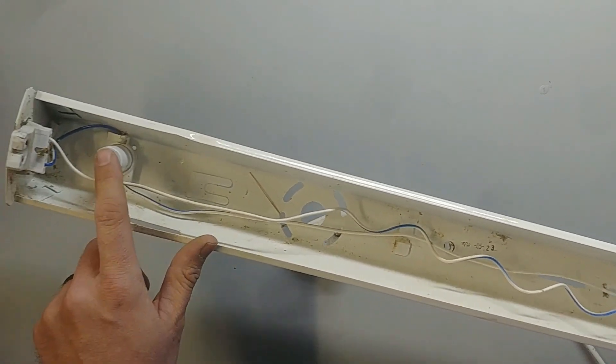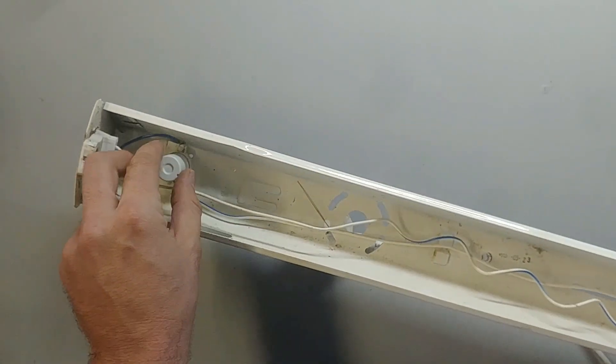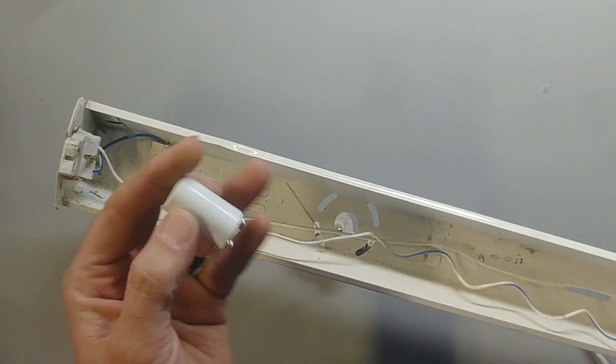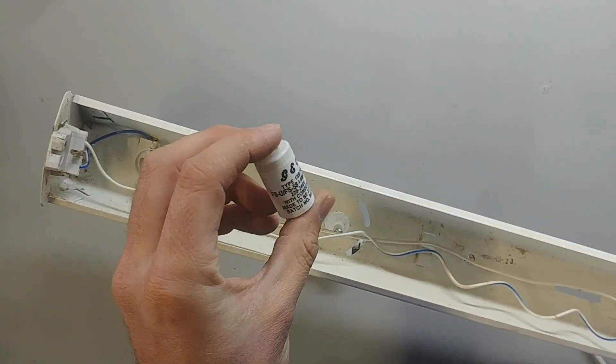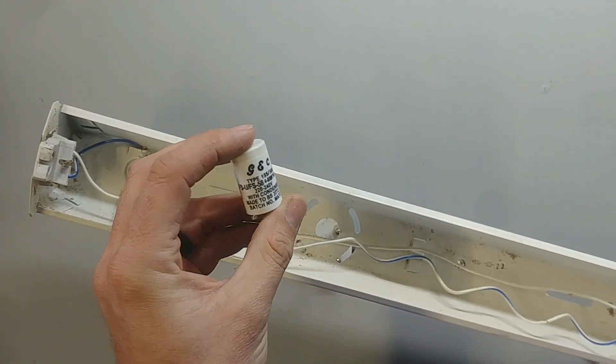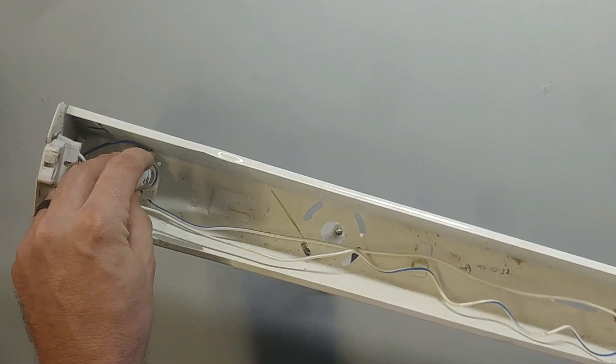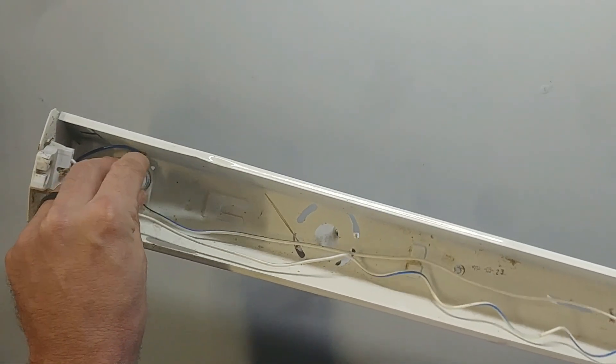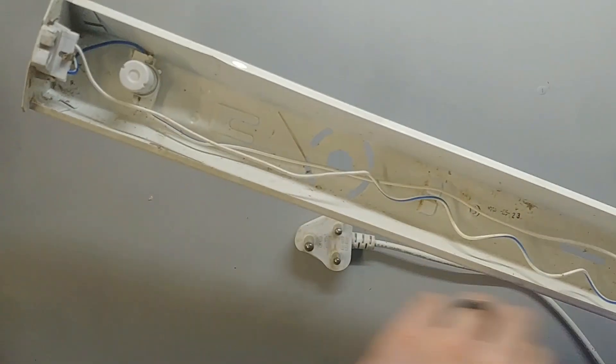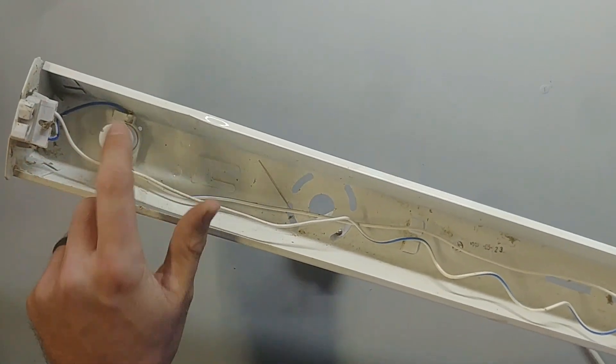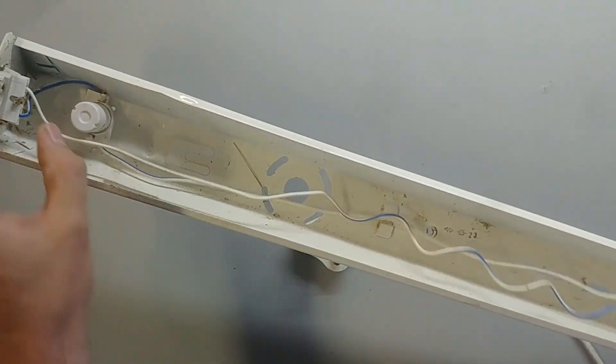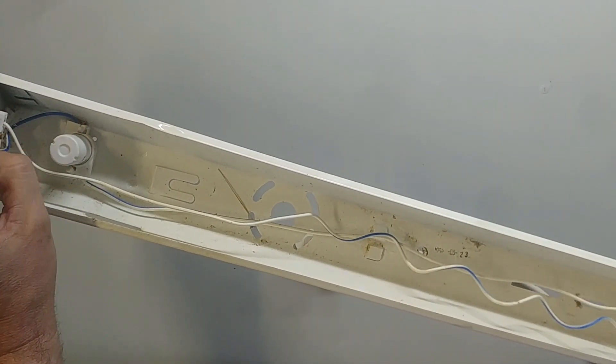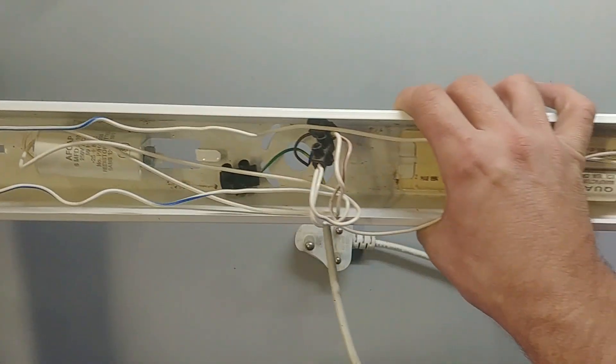So I'm going to use this side. Because some of these LED tubes come with one of these starters included. But they're not really a starter, they're only a fuse. So what you're going to do is just pop the one that comes with the LED tube, pop it in there, and you can use these two wires. And just connect these two wires, one to live and one to neutral.